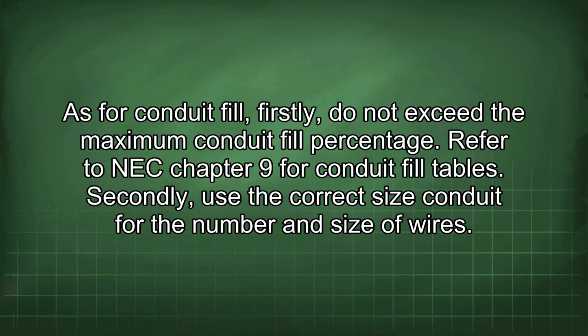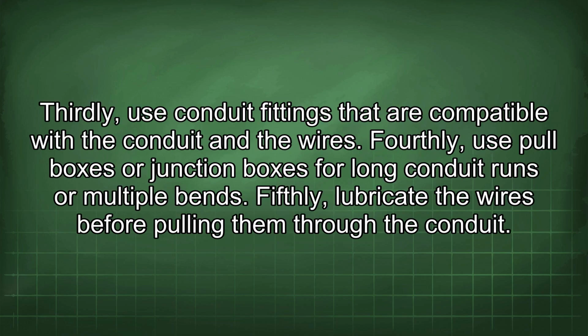As for conduit fill, firstly, do not exceed the maximum conduit fill percentage. Refer to NEC Chapter 9 for conduit fill tables. Secondly, use the correct size conduit for the number and size of wires. Thirdly, use conduit fittings that are compatible with the conduit and the wires. Fourthly, use pull boxes or junction boxes for long conduit runs or multiple bends. Fifthly, lubricate the wires before pulling them through the conduit.